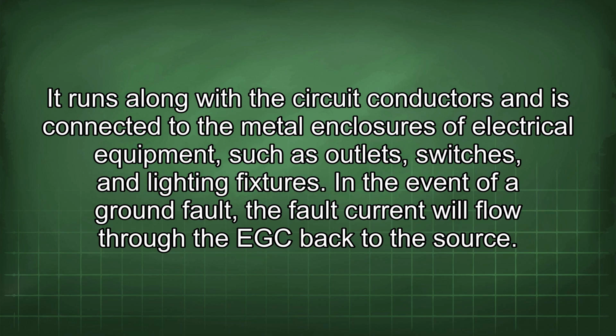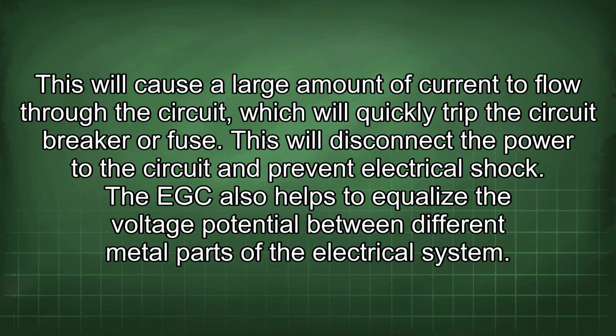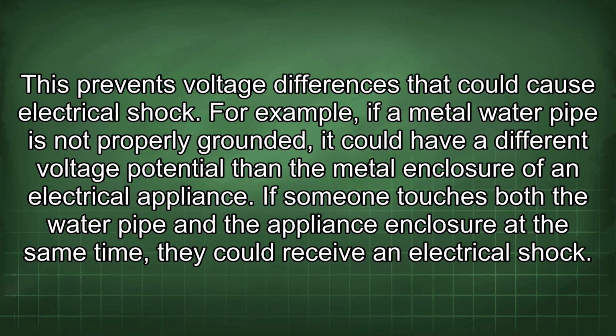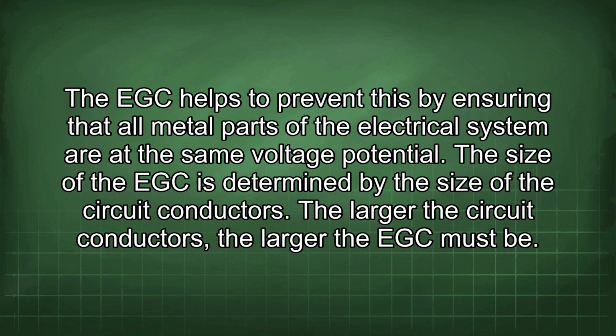In the event of a ground fault, the fault current will flow through the EGC back to the source. This will cause a large amount of current to flow through the circuit, which will quickly trip the circuit breaker or fuse. This will disconnect the power to the circuit and prevent electrical shock. The EGC also helps to equalize the voltage potential between different metal parts of the electrical system. This prevents voltage differences that could cause electrical shock. For example, if a metal water pipe is not properly grounded, it could have a different voltage potential than the metal enclosure of an electrical appliance. If someone touches both the water pipe and the appliance enclosure at the same time, they could receive an electrical shock. The EGC helps to prevent this by ensuring that all metal parts of the electrical system are at the same voltage potential.